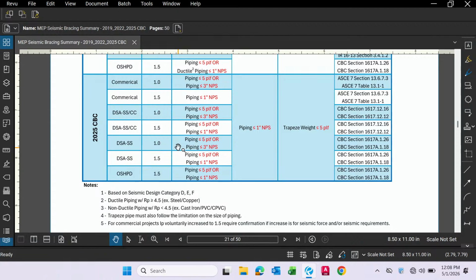Let's just concentrate on this first. When it comes to a commercial project with an importance factor of 1.0, piping that is less than or equal to 3 inch doesn't need to be braced. Okay, this table is the seismic exemptions. You don't need to brace anything that's listed on this table. The commercial building, right, 1.0 again, 3 inch or less, you don't need to brace it. Or, it says right here, if the piping weighs 5 pounds per linear foot or less. So even if your pipe is 4 inch and it weighs less than 5 pounds per foot, you can exempt that too. But for 4-inch pipe, usually it doesn't weigh less than 5 pounds per foot.